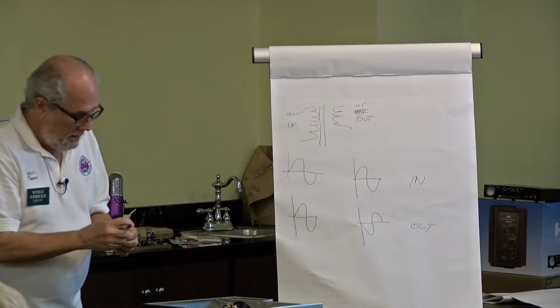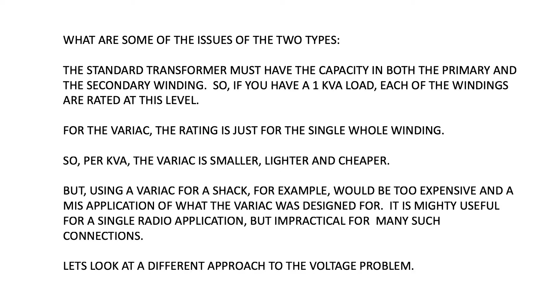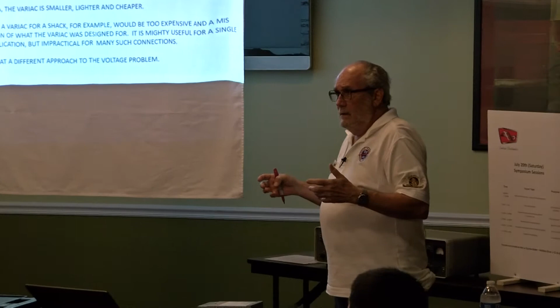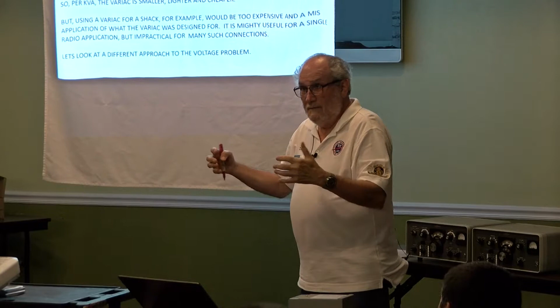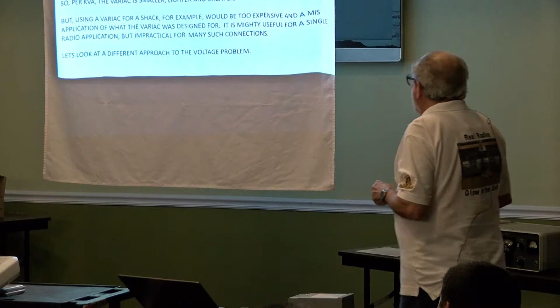The standard transformer must have a capacity in both the primary and secondary. We saw that—if you have a 1 kVA load, each winding is rated at 1 kVA. For the variac, the rating is just for the single whole winding, so per kVA, the variac is smaller, lighter, cheaper. But if you have a shack with multiple outlets, a variac for your whole shack would be very physically large.